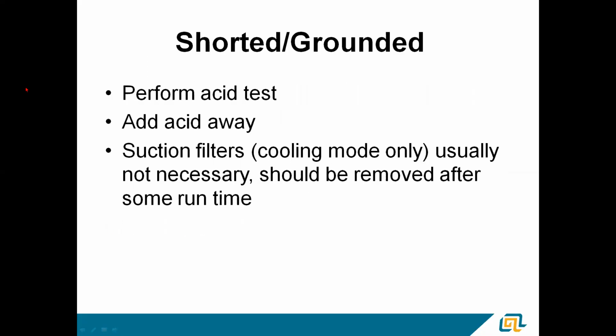If the compressor was shorted or grounded, definitely perform an acid test. We sell little acid test kits. You get a little oil out of the system, check it and make sure it isn't acidic. If it is, there's a product called Acid Away, an acid scavenger. It is the only additive Trane or American Standard approves being put in their system. So Acid Away is a good little thing to do. Truthfully, you dump it in the suction line of the compressor before you braze it in, which is the easiest way to introduce it to the system.